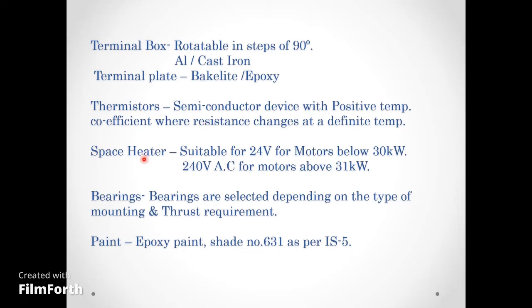A space heater is provided inside the motor for anti-condensation purposes. For motors below 30kW, the voltage is 24V; for motors above 30kW, it is 240V AC. Bearings are selected based on the type of mounting and thrust requirements. Paint used is epoxy, shade 631 as per IS5.